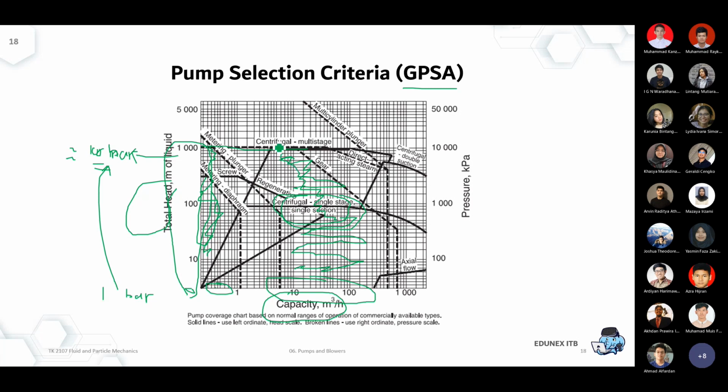But now let's say you were working with a very high condition, still the same flow rate, but now you need to compress more than 100 bar. So you are now in multi-stage. That will correlate to around 100 to 500 bar. Maybe it's not enough to use one stage of impeller. Instead, you have to use 2 or even 3 stages of impeller. For example, I think this is the CO2 injection pump in a lot of CO2 EOR and CCS projects.